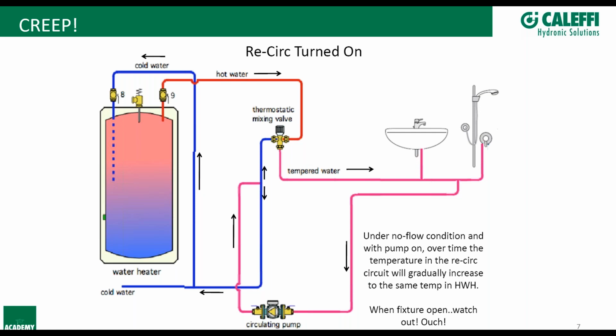And the idea with recirc creep is that if you are running a constant recirculation system in a building and you're using a thermostatic mixing valve, it doesn't matter if it's our mixing valves or anybody else's, you can actually run into scenarios where your distribution loop and your recirc line will come up to whatever the storage tank temperature might be. So if you're running 150 degrees in this storage tank, you actually have the ability to bring up this distribution line and your recirc line all the way up to 150 during times of no demand. And the reason why that happens is you look at this very simple drawing here.